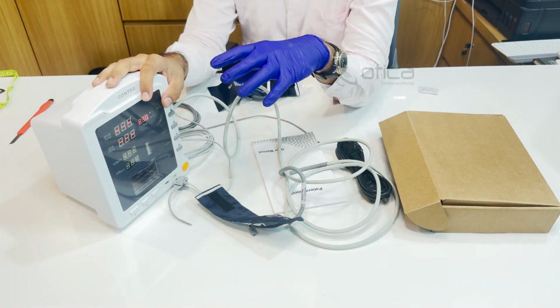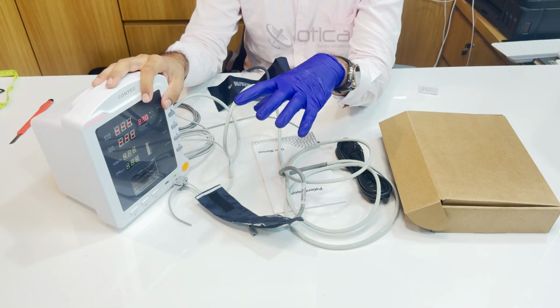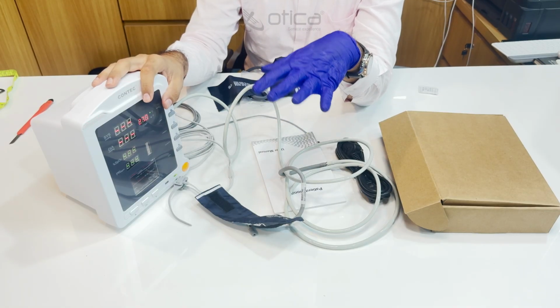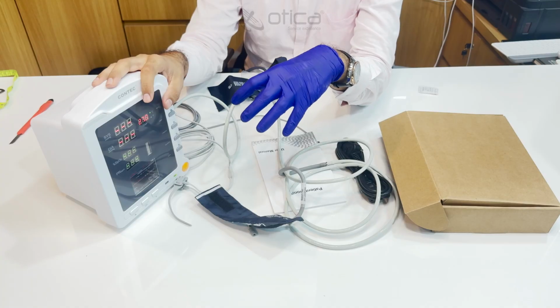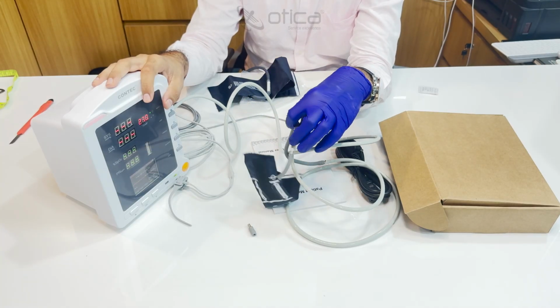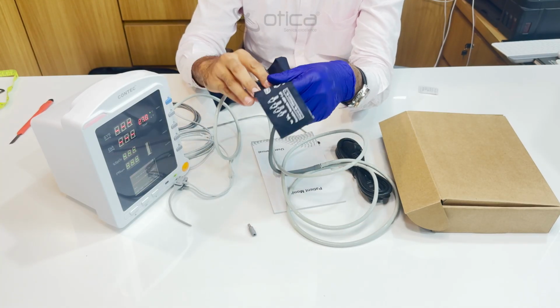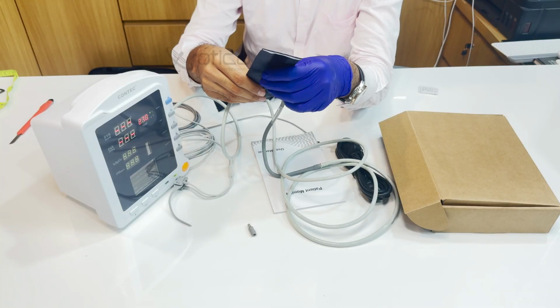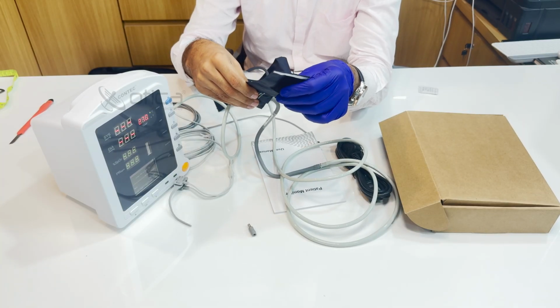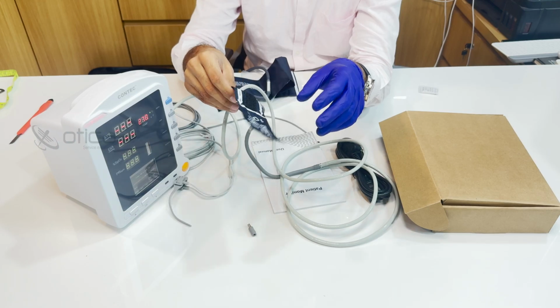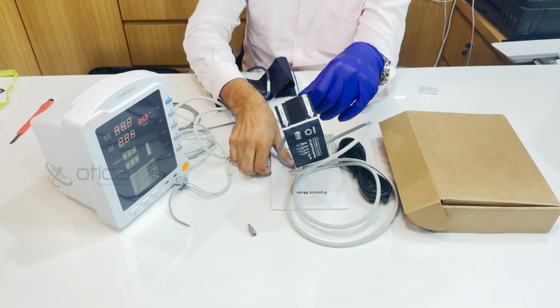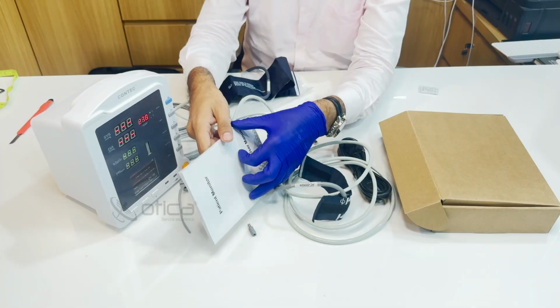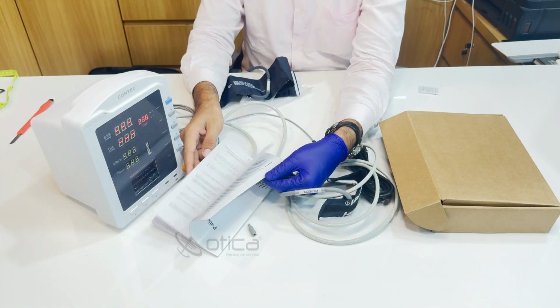It is very important to change the patient type, otherwise it will cause damage to the baby. If the patient type is adult and you have attached the neonatal cuff, the pressure in the neonatal cuff will be very high and it will damage the neonatal patient. So make sure you change the patient type and read this menu carefully.